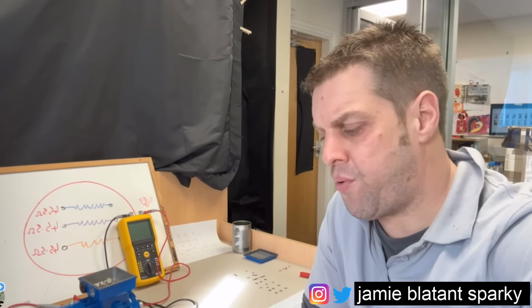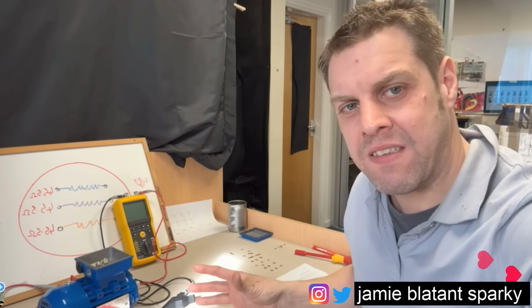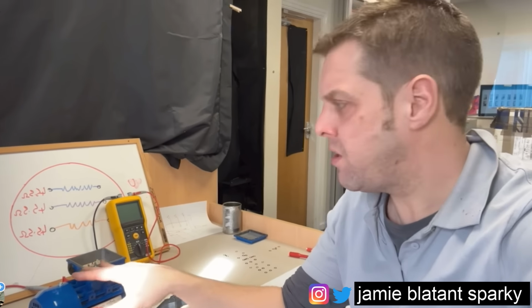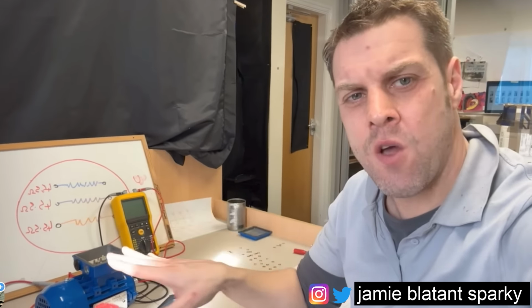Now, I appreciate that was a very, very long video and we didn't actually spend that long with testing. And to me, that's the whole point, is the results are just results, they're just numbers. But knowing what's going off in your drawing and knowing what's going off inside the motor, and using those results that you get very quickly and thinking how they react to that drawing and what the actual internal things are going off inside the motor, is the secret sauce, yeah? The testing is just putting some probes on and pressing a button. Knowing what's happening inside is the secret sauce.